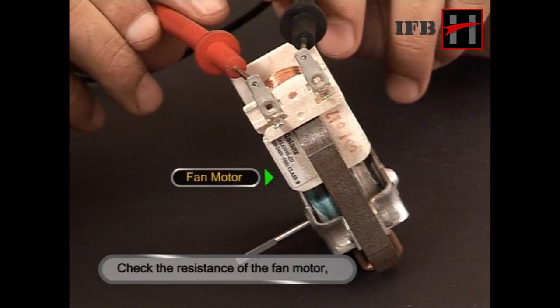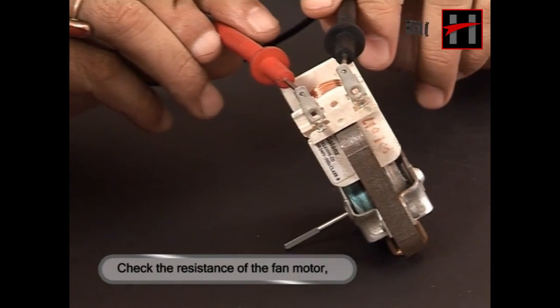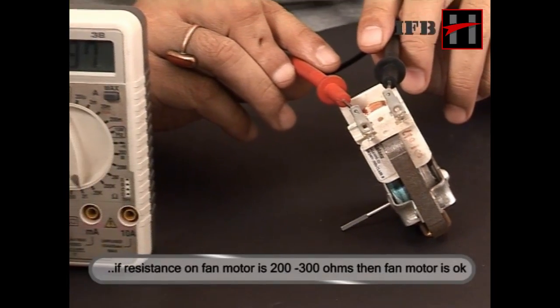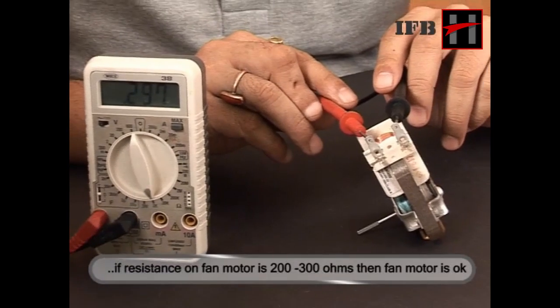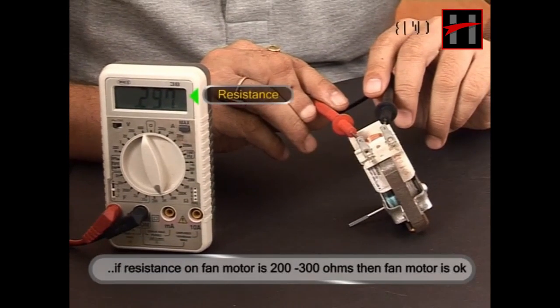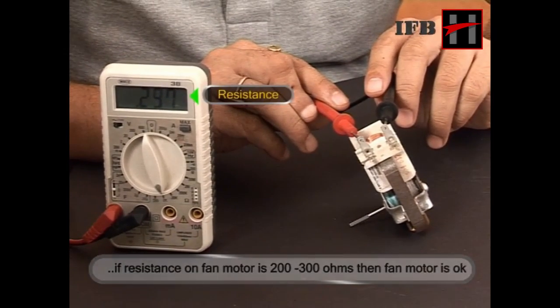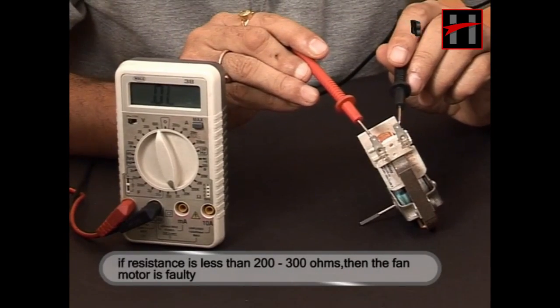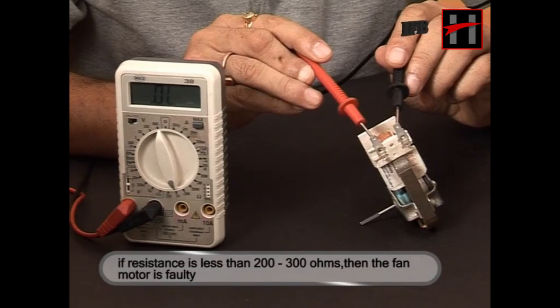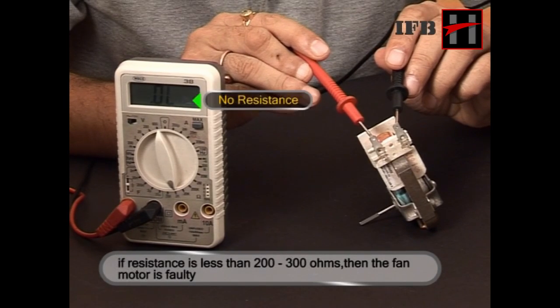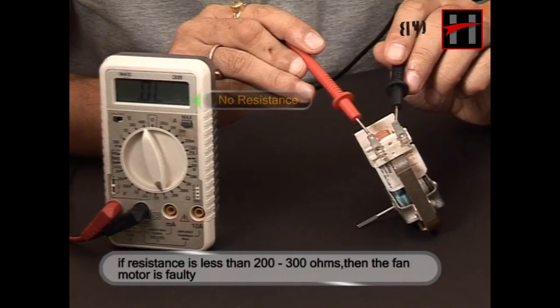Check the resistance of the fan motor. If resistance on fan motor is 200 to 300 ohms, then the fan motor is OK. However, if resistance is less than 200 to 300 ohms, or if resistance is not present, then the fan motor is faulty.